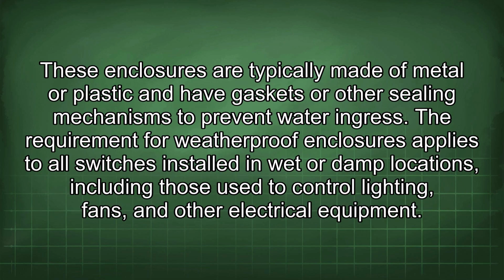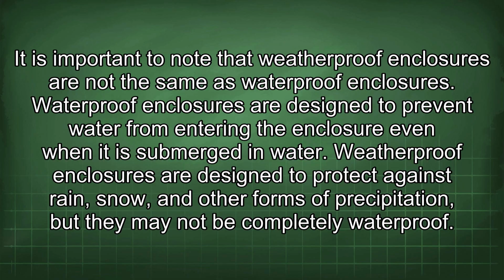These enclosures are typically made of metal or plastic and have gaskets or other sealing mechanisms to prevent water ingress. The requirement for a weatherproof enclosure applies to all switches installed in wet or damp locations, including those used to control lighting, fans, and other electrical equipment. It is important to note that weatherproof enclosures are not the same as waterproof enclosures.